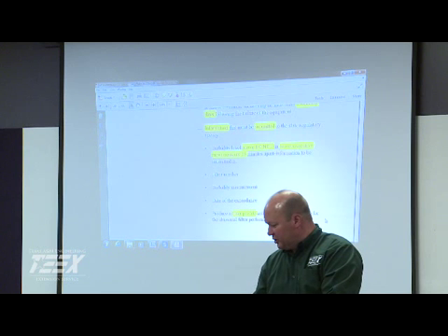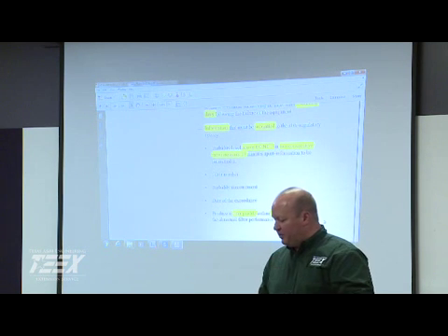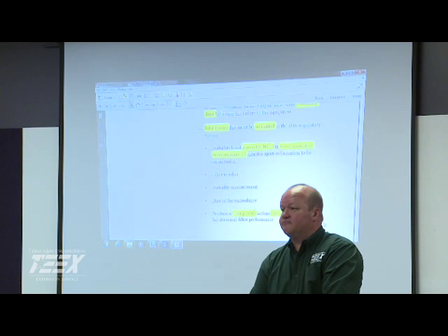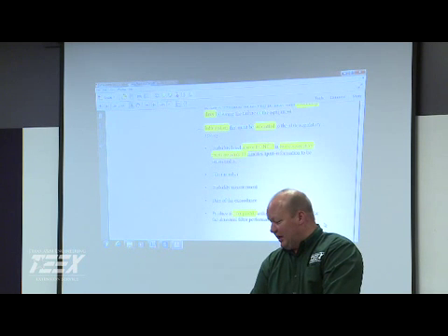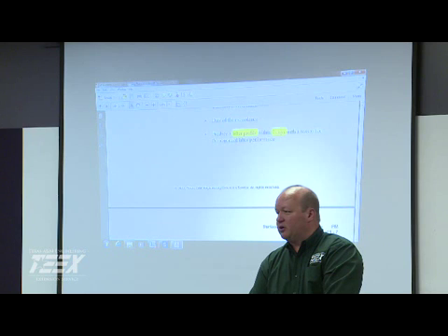And then anytime you do have these issues, you've got to submit to the regulatory authority, and it's important to include them. If you have turbidity issues over 1 in 2 consecutive 15-minute measurements, then you're going to have to start doing your filter profiles. We've actually got that at 0.5 instead of 1. Excellent. More stringent is better for your consumer. Ultimately, that's what we're trying to do, make it the best that we can. You've got a 7-day window on that one also? Yeah, I believe so.